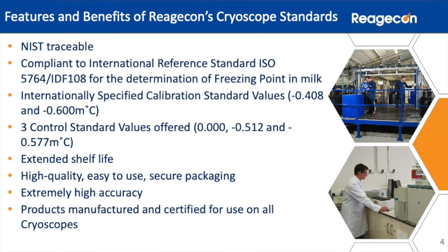Reagecon's cryoscope standards offer significant technical advantages over the products produced by any of our competitors. The products are NIST traceable, compliant to the International Reference Standard ISO 5764 IDF108 for the determination of freezing point in milk. We offer all internationally specified calibration values, control values, extended shelf life, and the products can be used on every make and model of instrument. More detailed technical information and specific product information can be obtained at www.riagecon.com, either through our webshop or our Knowledge Centre.